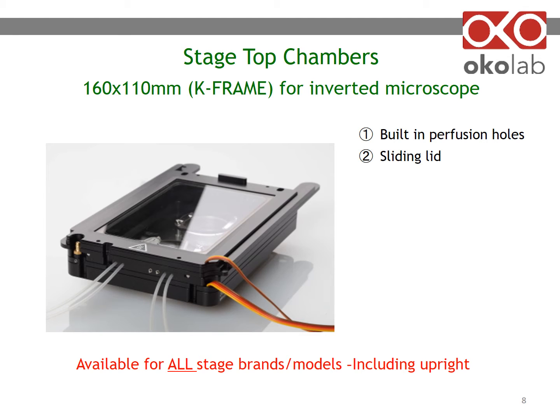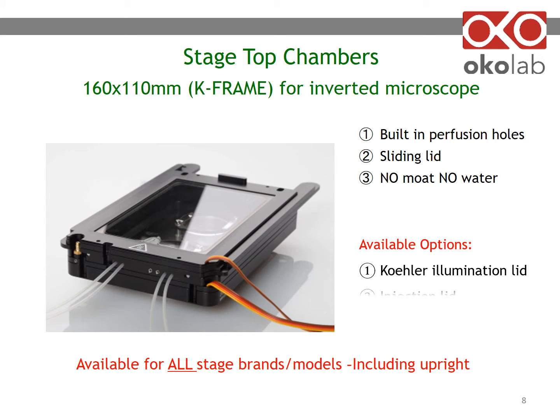The lid slides open, and you do not have to put water inside the chamber to provide humidity — there is no moat and no water. Several optional lids are available for the K-frame chamber: a Koehler illumination lid allowing you to focus the condenser, an injection lid for the insertion of capillaries, or a laser interlock lid for laser safety.